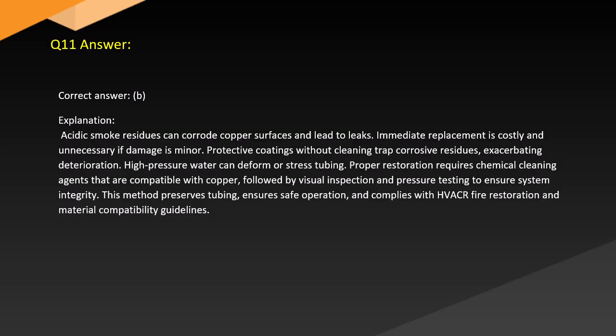Immediate replacement is costly and unnecessary if damage is minor. Protective coatings without cleaning trap corrosive residues, exacerbating deterioration. High-pressure water can deform or stress tubing. Proper restoration requires chemical cleaning agents that are compatible with copper, followed by visual inspection and pressure testing to ensure integrity. This method preserves tubing, ensures safe operation, and complies with HVACR fire restoration and material compatibility guidelines.